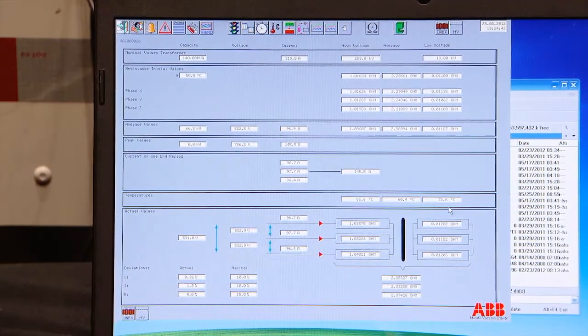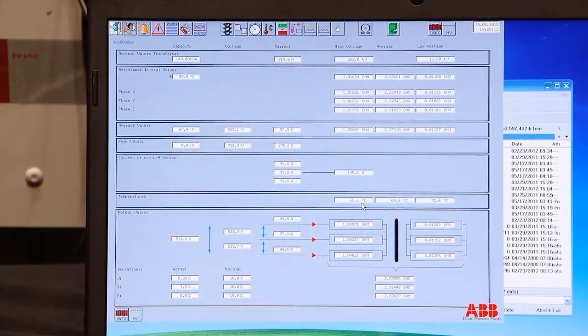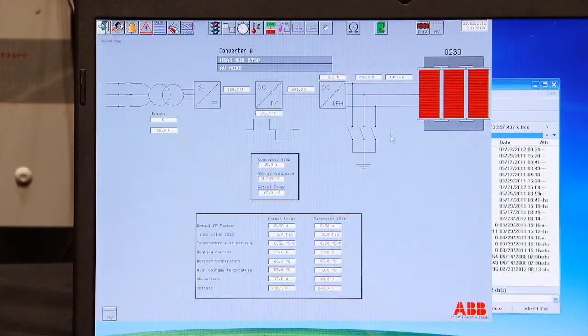So we were taking our temperature readings. We were at 60 degrees average, high voltage 55 degrees, low voltage 72 degrees. So even at this small temperature step, the temperature difference came quite high. We are measuring the high voltage, we are measuring the average resistance. Resistance temperature, that's the same. We are calculating the temperature based on the resistance. So what we do now is that we continue heating up the average up to 65 degrees, from 60 up to 65, and that's where we will do the stabilization.